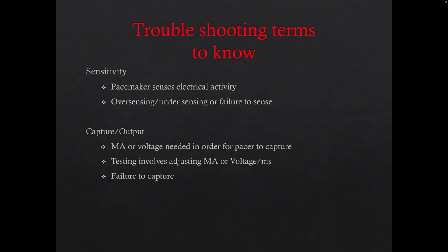Undersensing means that it doesn't see it and it's delivering output. And where would that be bad? What happens if you undersense, it doesn't see the patient's own signal, and then it paces? I think I talk about it later, actually. It can cause premature beats, but what happens if you get an R-on-T phenomenon? If the ventricle paces smack on the T wave, during what we call refractory, it causes them to go into VT. Really bad situation.